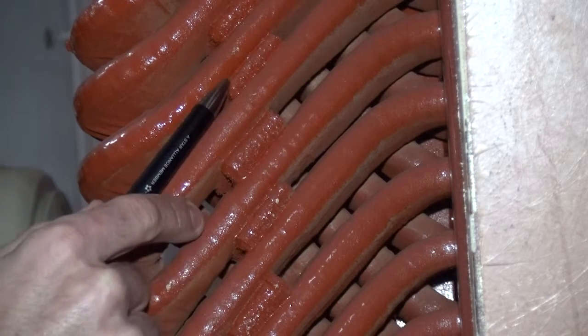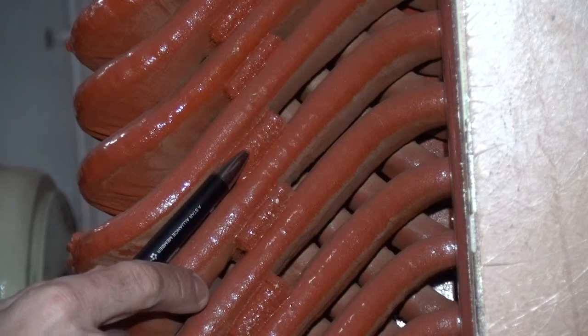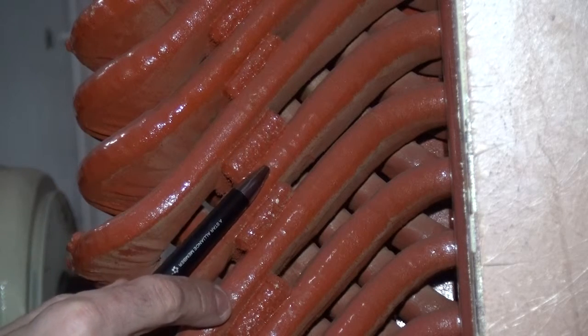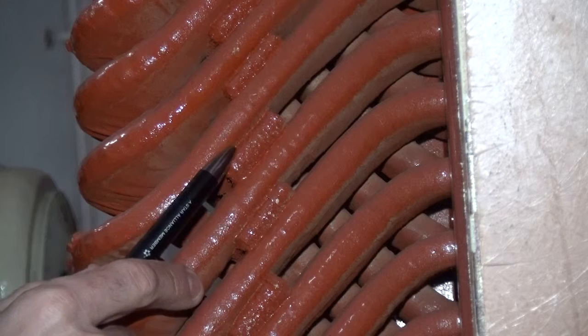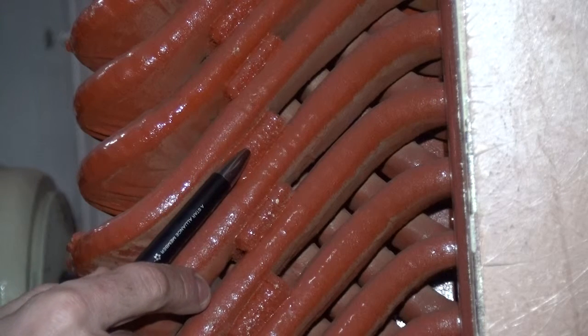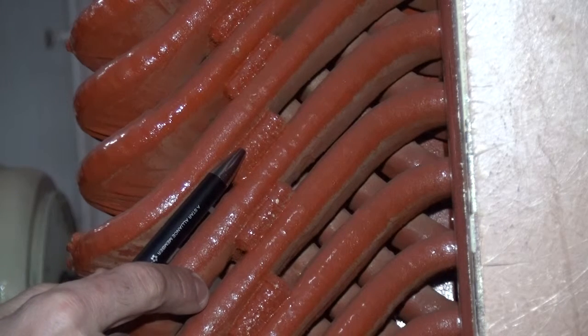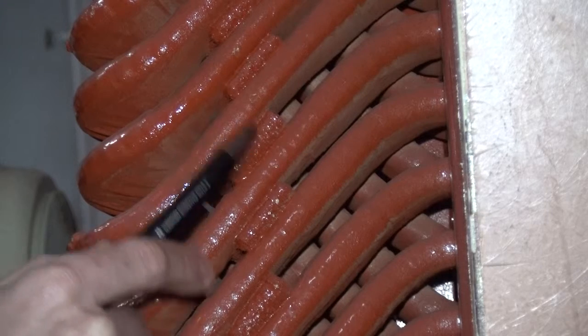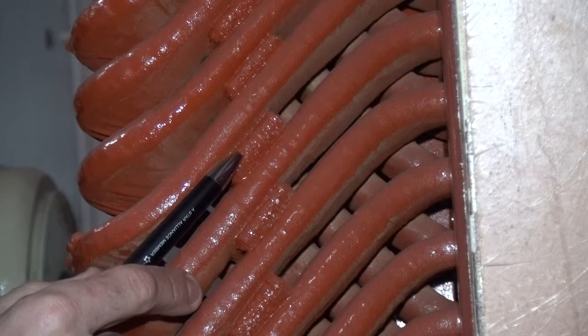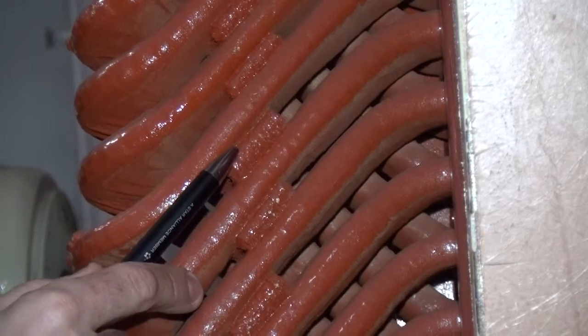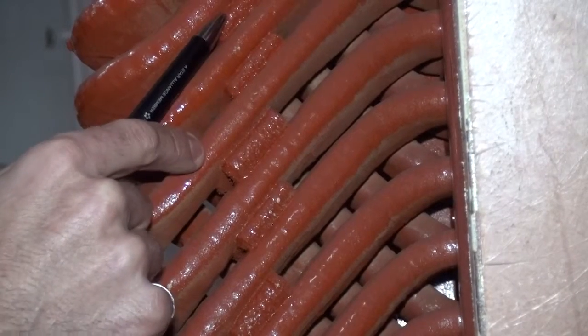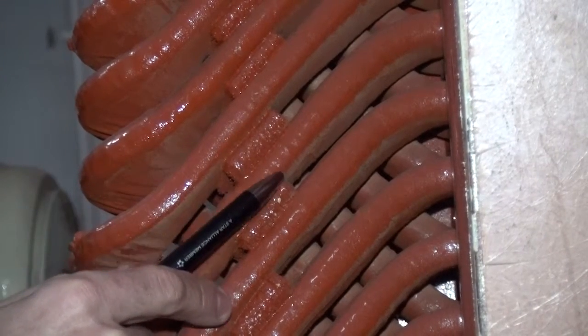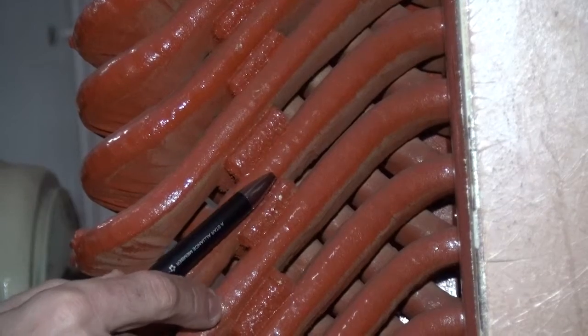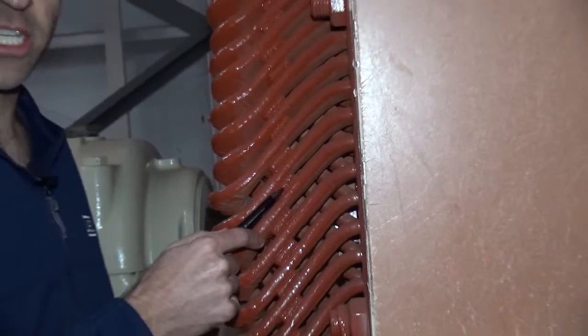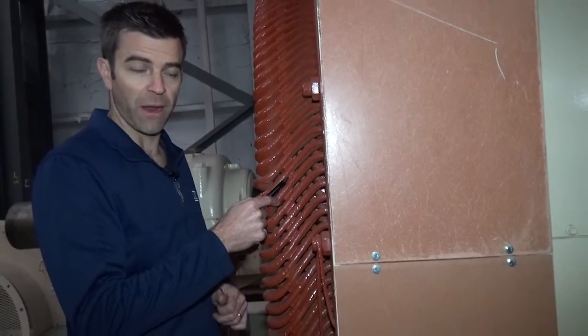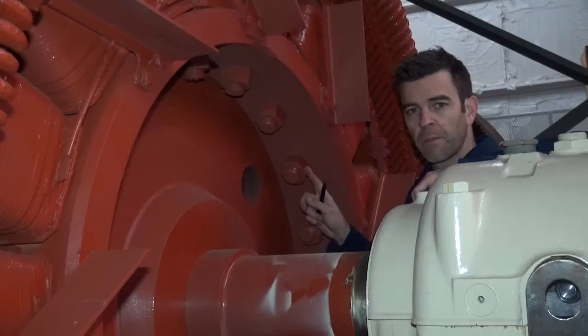Here we have pieces of blocking or felt which have been inserted in between adjacent stator coils, but there is no lashing which has been wrapped around it. Larger machines, especially high voltage and turbo generators, will have lashing which is wrapped around the coils, and that's used for extra reinforcement. Inspect all blocking for loose or missing blocks and take photographs of any which are not in ideal condition. This will be a future repair.